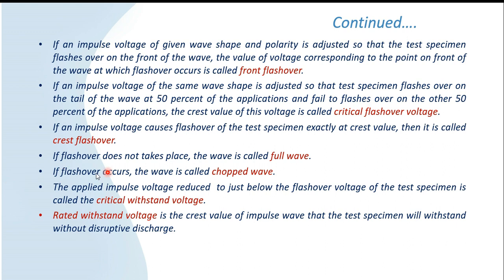The main terms associated with the volt-time curve are front flashover, crest flashover, and critical flashover voltage. If flashover does not take place the wave is called a full wave, and if flashover occurs it is called a chopped wave. If the applied impulse voltage is reduced to just below the flashover voltage of the test object, then it is called the critical withstand voltage. The rated withstand voltage will be below the flashover voltage.